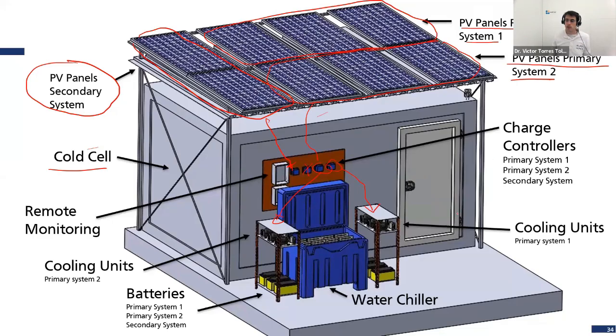You see here the charge controllers. You see the cooling units. This is the water chiller. The water chiller is for us the ice storage. So we have here the ice, and then the cold water is pumped inside the cold room. Then we have batteries for the 2 primary systems and for the secondary system. The primary systems, as I told you, don't necessarily need them, but we normally install small batteries for the primary system too, because of the reasons mentioned before.